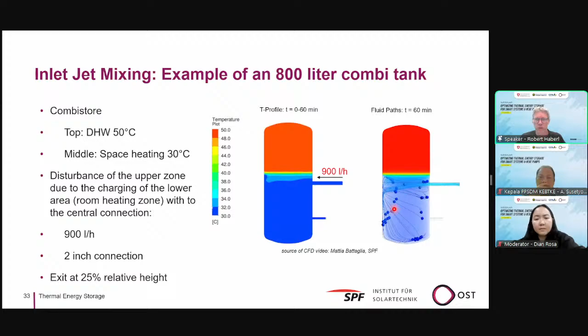There are different methods to slow down the speed of the fluid, and it's also important that after you have a change in direction of the flow, you have to calm down the fluid, meaning you have to have a diameter of a pipe that is big enough to have a low velocity below 0.1 meter per second, but the length of that pipe is also important. You see here the pipe feed to the storage tank, then it divides into 2 branches, and the length varies in different CFD simulations.